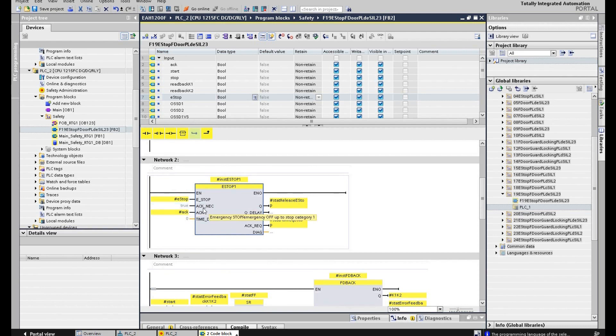The acknowledge necessary is set to true, which means if the e-stop is pressed the output will go off, and after the e-stop is released the output of this function block will not recover automatically. We must click acknowledge to recover the safety status. After the acknowledge, the output of this function block will recover from off to on. That is the e-stop.